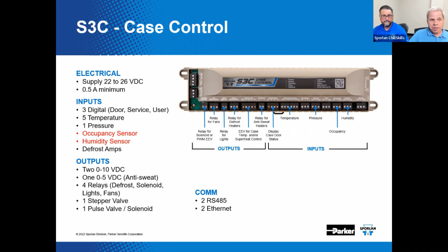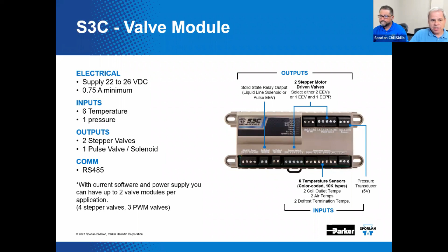Here is the S3C valve module. Now, the valve module is simply an extension of the base controller. It expands the control capabilities of the S3C control system by providing additional input and output if there's a requirement for more complex applications. Let's say you've got more devices you need to terminate on the control, or you have additional evaporators in that refrigerator case. Right. The only reason you need this is if you run out of input or output capacity on the S3C itself. But as we already just discussed, the S3C itself has quite a bit of capacity. So you can look at this as an extension of the actual devices.